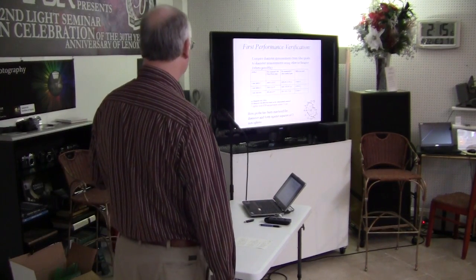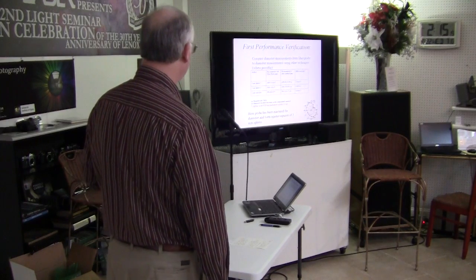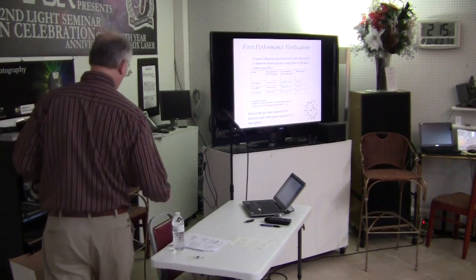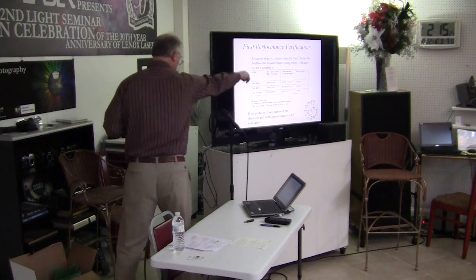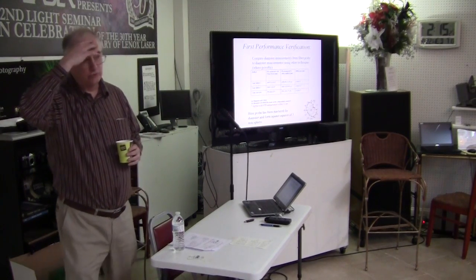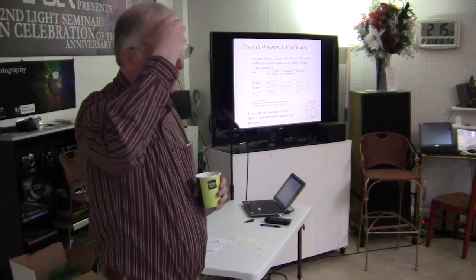And here, we're measuring a 5 millimeter sphere down to a 1 millimeter hole. These were measured by us and PTB, which is the German National Laboratory. They have a machine. They have a fiber probe also. Their fiber probe comes out and bends down, and they have a microscope to look at the ball. We look at the stem, they look at the ball. That's the major difference. Turns out it's nicer to measure this probe because the balls eventually get too small to really see well.